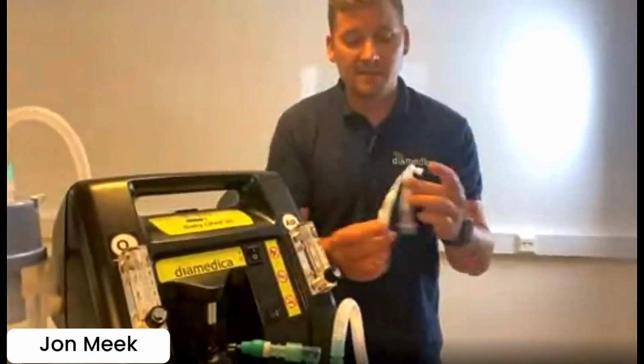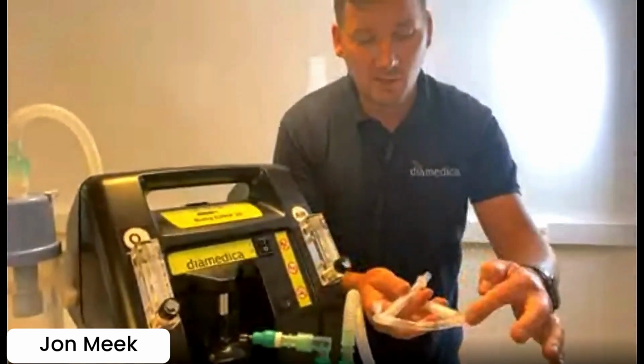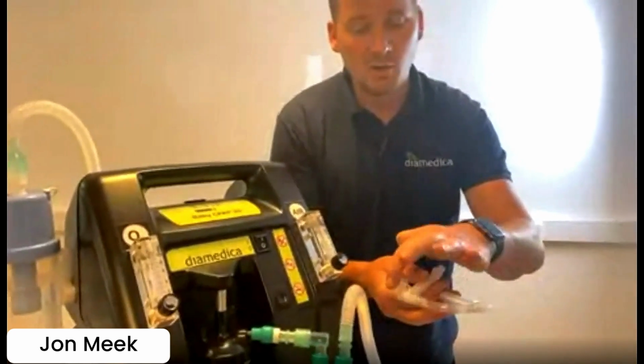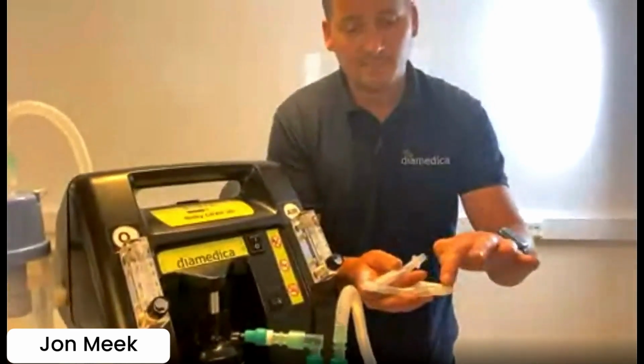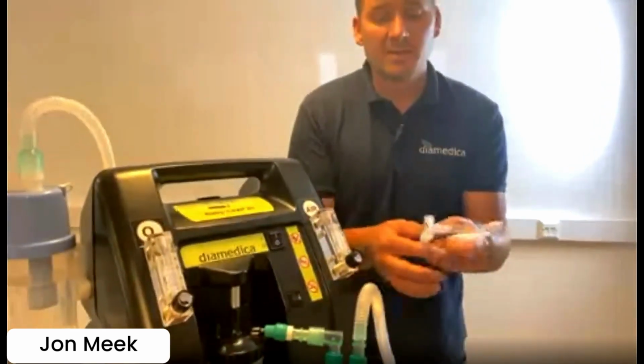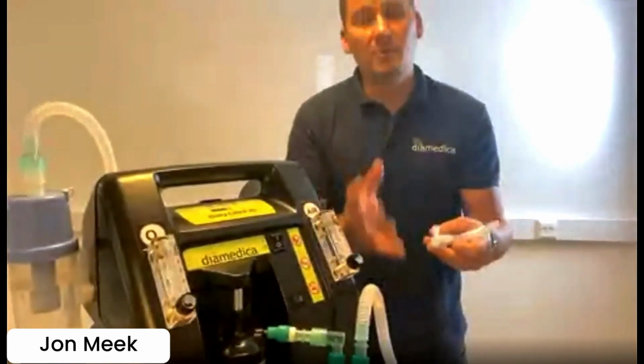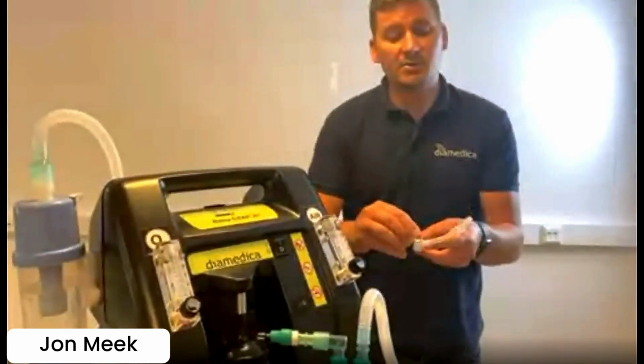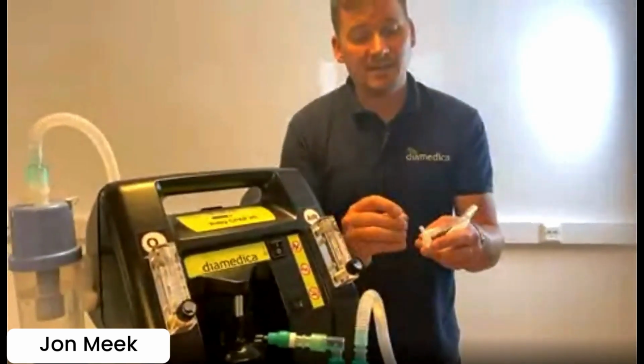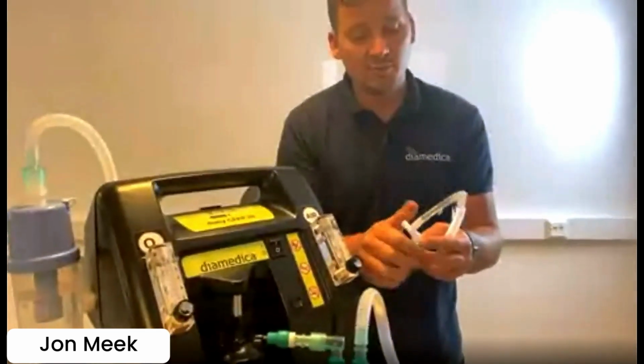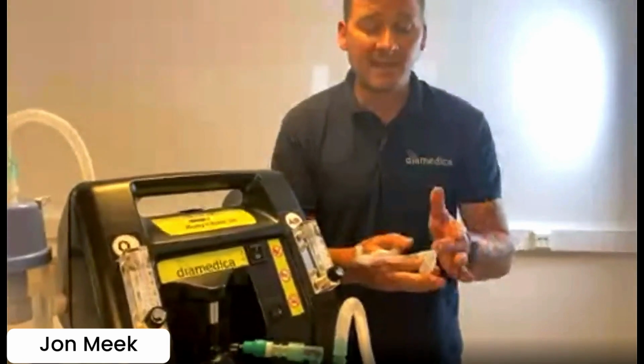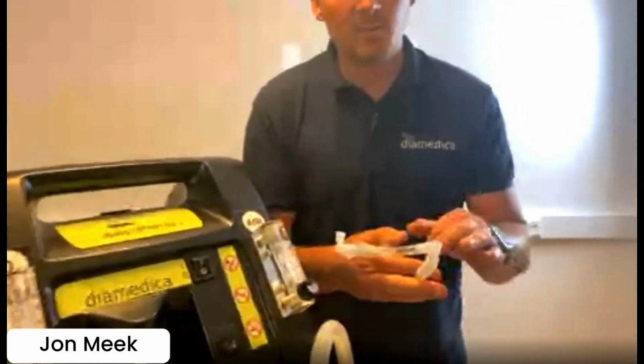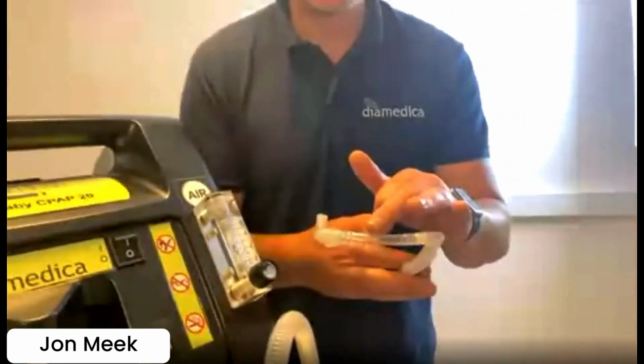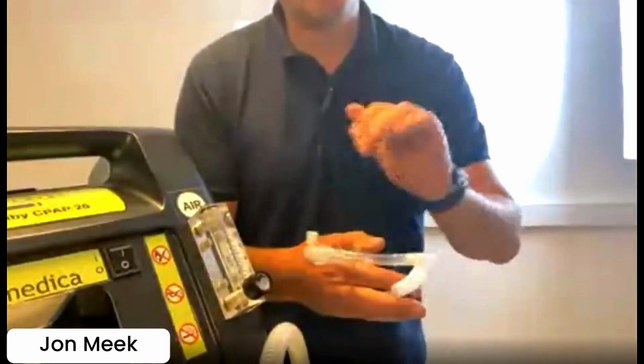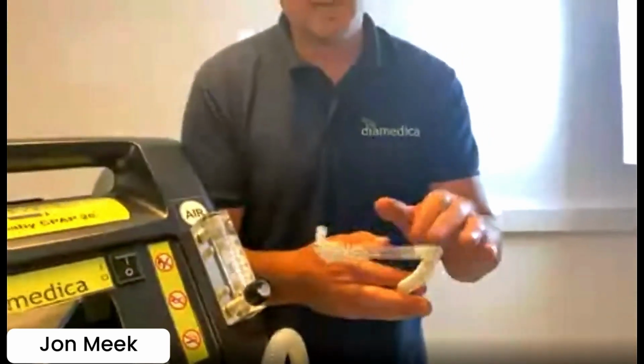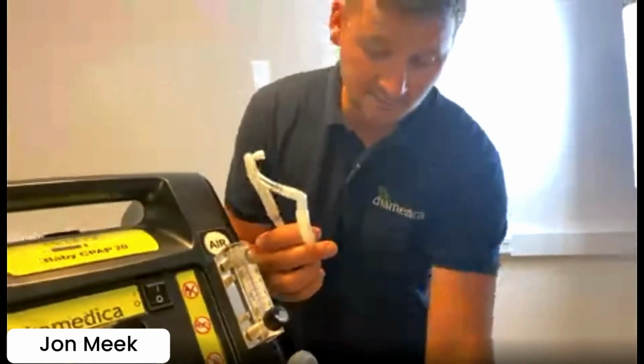Once they are fitted, you can see there's two differences on each elbow here. One has a luer lock sampling line connector and the other one doesn't. The sampling line connector, if you have it, is a CO2 sampling line, and it must be connected on the expiratory tube. If it's connected on the inspiratory, then you'll have fresh gas flow going over it, and you won't be reading any CO2. So it needs to be on the expiratory side.